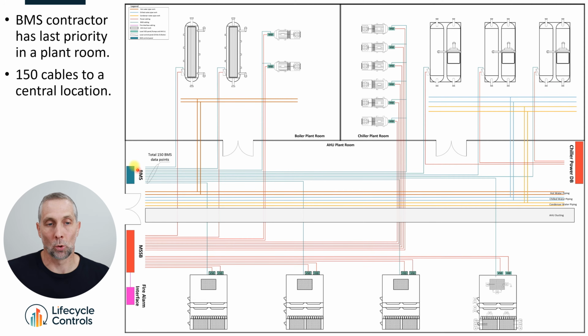So we install this centralized BMS panel. In Australia, we normally have our panels separate from the mechanical boards because it's two different companies. But in a lot of countries, for sure, where the BMS is also the mechanical electrician, you'll be putting the BMS controllers in the mechanical boards. There are some companies in Australia that do that, but generally in Australia, the BMS control panel is separate. So we have this centralized BMS control panel that we've got to get 150 cables to from the boiler plant room, the chiller plant room, and the 4 air handling units.